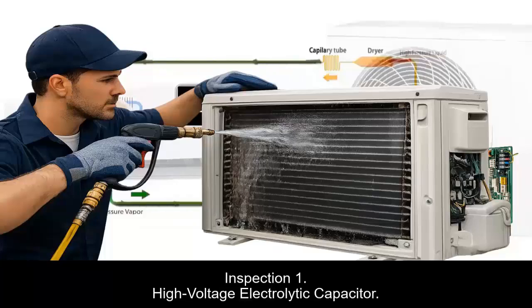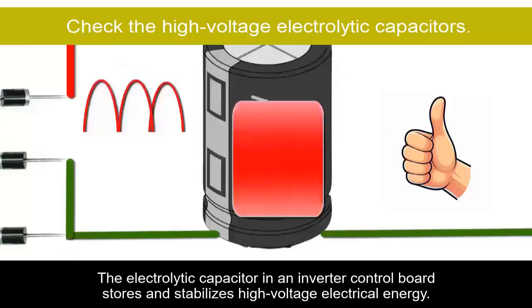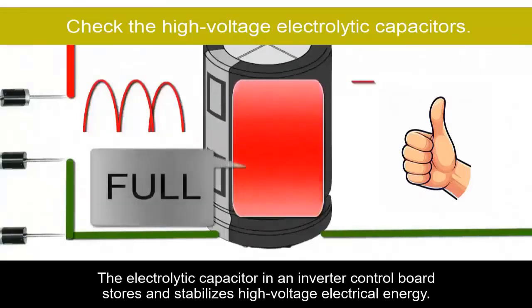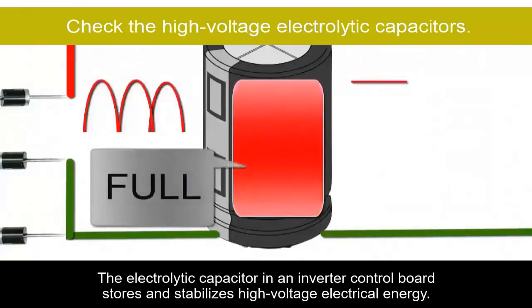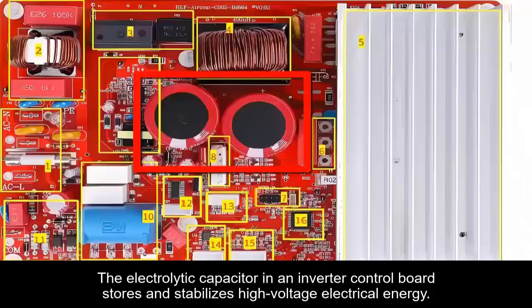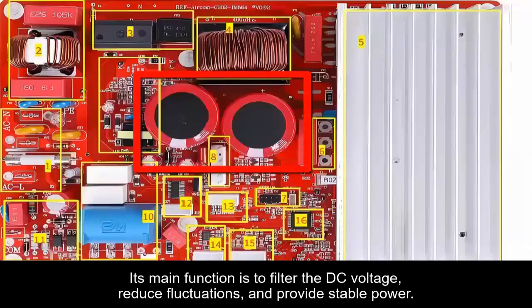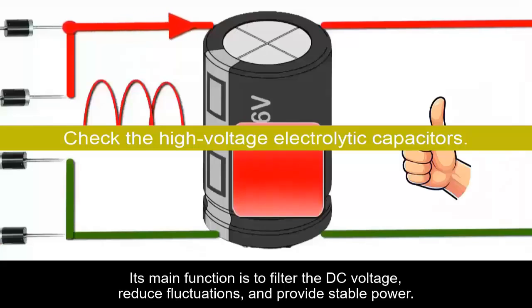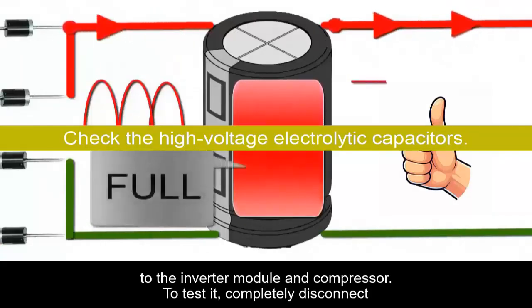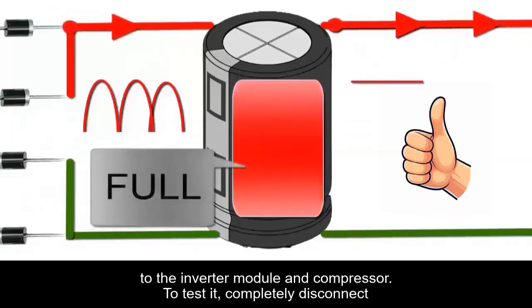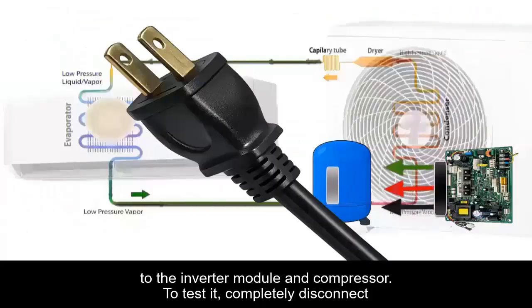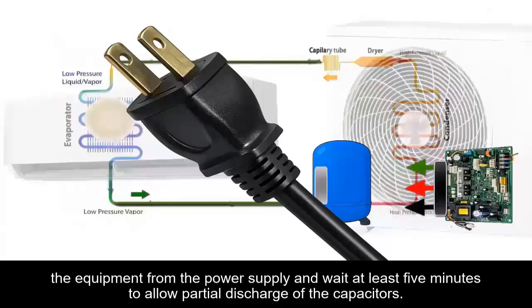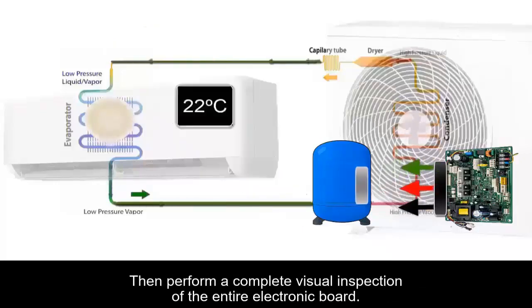Inspection 1. High voltage electrolytic capacitor. The electrolytic capacitor in an inverter control board stores and stabilizes high voltage electrical energy. Its main function is to filter the DC voltage, reduce fluctuations, and provide stable power to the inverter module and compressor. To test it, completely disconnect the equipment from the power supply and wait at least 5 minutes to allow complete discharge of the capacitors.